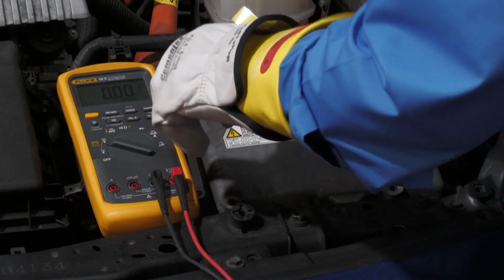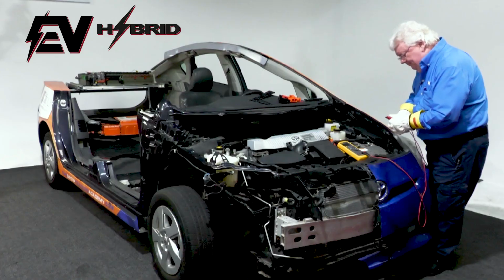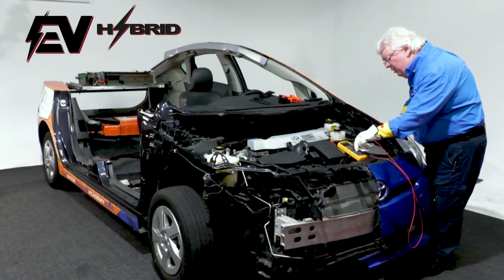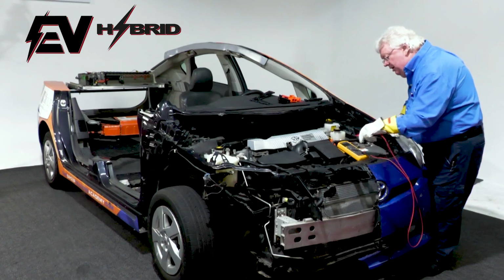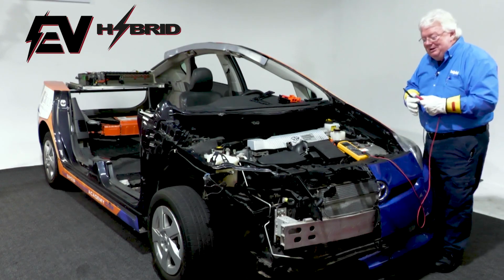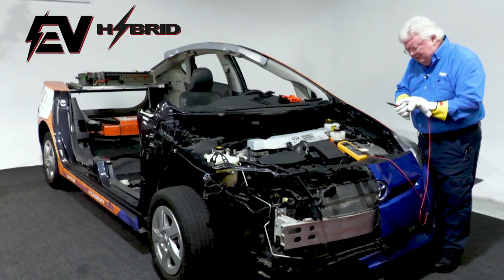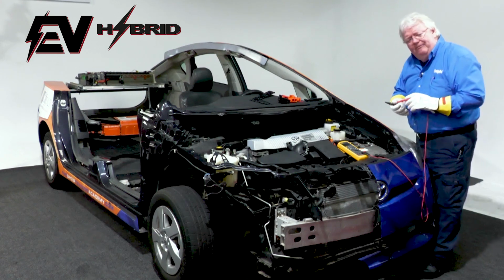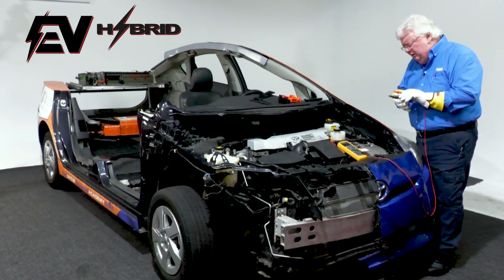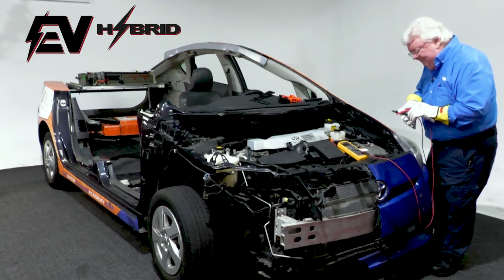I've got to get my meter out of manual ranging and put it into auto range. There we go, because I know this particular meter will fool me and say there's no voltage there. So it's very important you have a high voltage proving unit and a way to do a live, dead, live test very accurately.